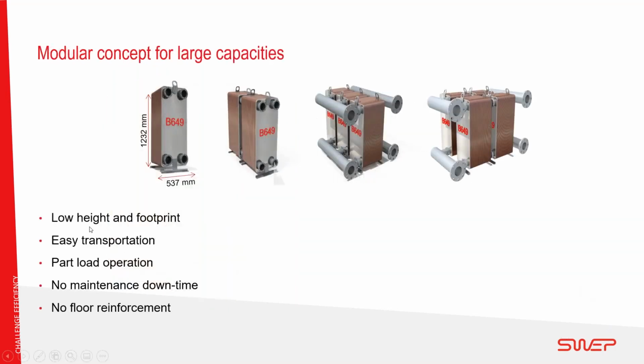So here we've got the modular concept. You can see we've got it in serial and parallel configuration. So not only does it have a very high capacity as a single unit, but with our design tool, we can link it together. And so you get all the benefits of a compact unit, but in a modular solution. So of course, there's a much lower footprint relative to the kilowatt load output of the heat exchanger compared with, say, gasket technologies. And as you'll see in some of the case studies a little bit later on, the compact size makes it a bit more maneuverable on site.